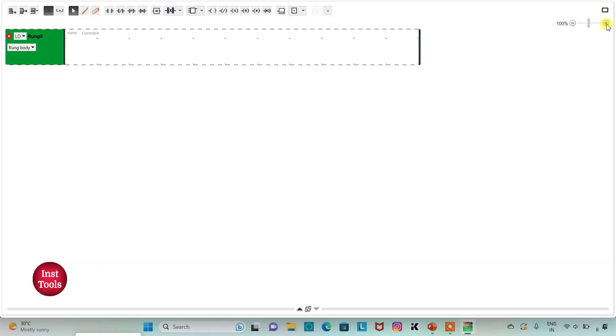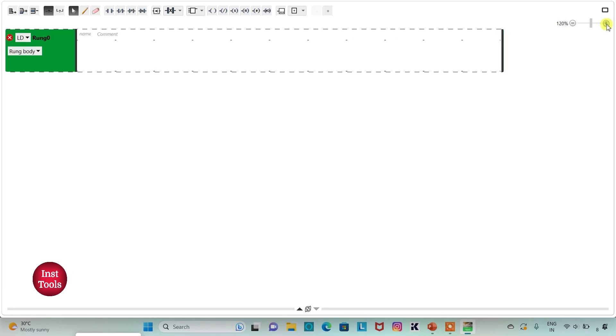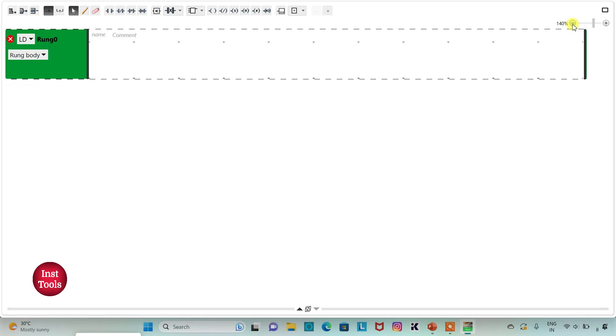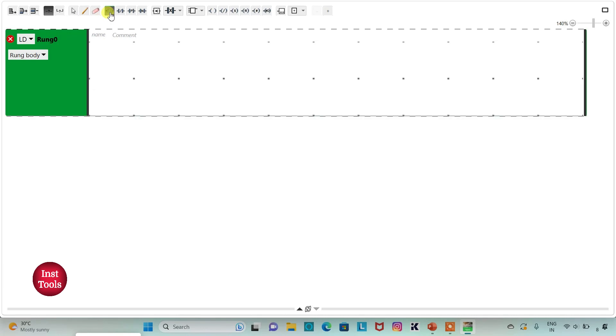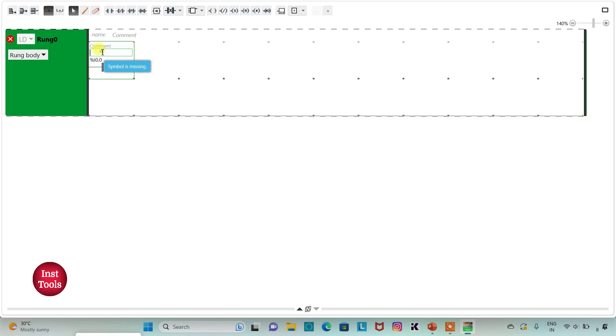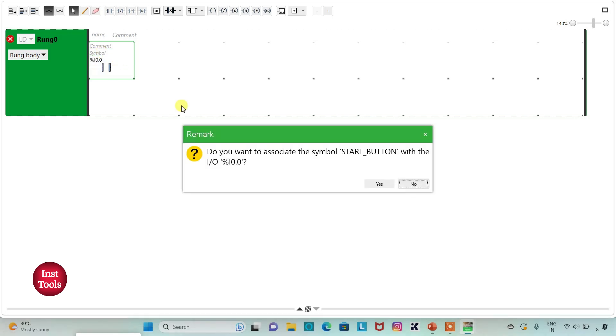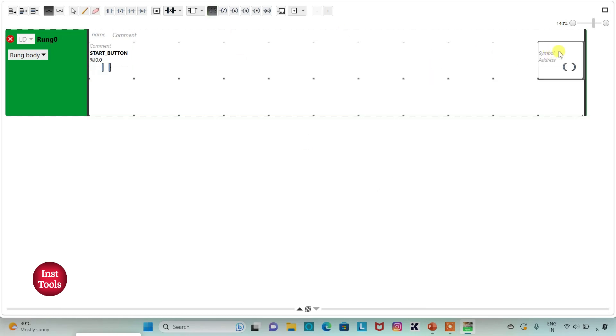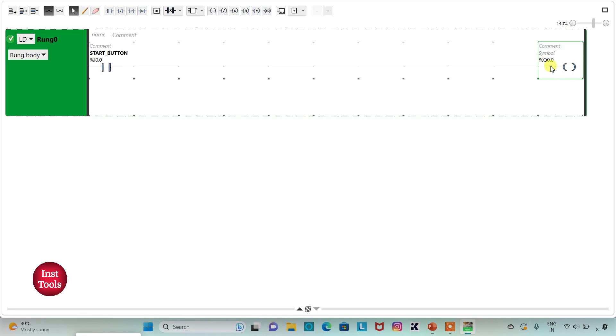I can zoom in by clicking on the plus button or zoom out by clicking the minus button. First, I will insert a normally open contact here and I will assign address to it as %I0.0. I will also add symbol to it as start button. Then I will insert a coil here and I will assign address to this coil as %Q0.0. I will also add symbol to it as pump.